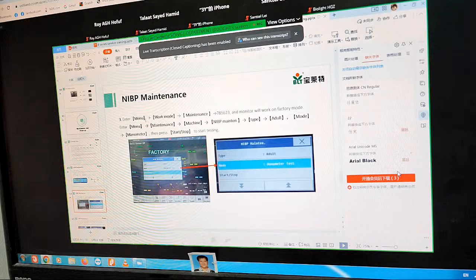The first step is to go to the menu and work mode. You need to choose the maintenance work mode and enter the password, and the monitor will go into factory mode. Choose the mode, choose the menu again, go to maintenance, and choose machine and NIBP maintenance. Choose the type for adult, set the mode to manometer, and then press start or stop to begin the test.